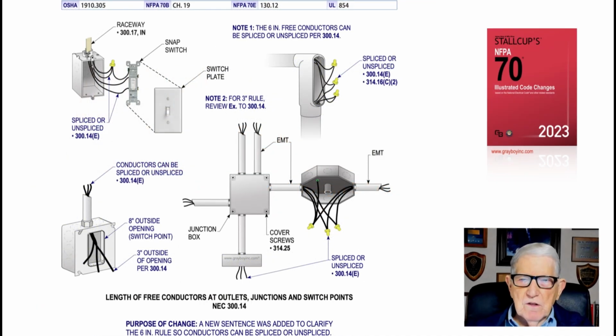Now this illustration deals with the length of conductors at outlets, junctions, and switch points. Mainly it's just to have enough conductor length to make a connection without the length of the conductors being too short. Now, the purpose of the change: a new sentence was added to verify the 6 inch or 3 inch rule, really. But now if you notice in the illustration, left hand side top of the illustration, we have a raceway and we have a box here.